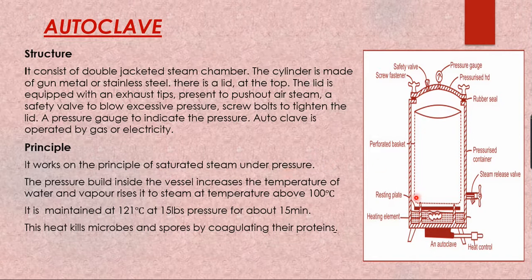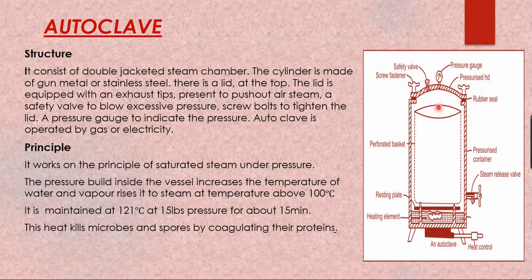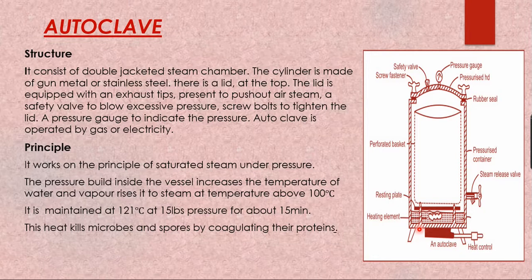In the working mechanism, once switched on, water is boiled and steam raises, creating pressure. The pressure built inside the vessel increases the temperature of water and vaporizes it into steam above 100°C. The autoclave is maintained at 121°C at 15 lb pressure for about 15 minutes. When the pressure gauge reads 15 lb pressure, that indicates the temperature inside is 121°C, and from that point you note the time for 15 to 20 minutes.